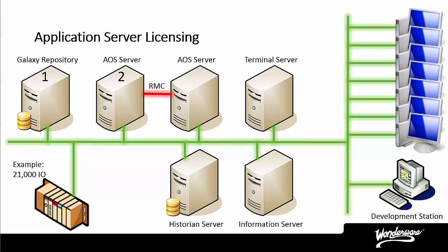The Galaxy Repository is always the first platform in the application. The AOS computer runs objects that represent pieces of equipment or functions to be performed. If you would like a more reliable system, you can add a second AOS computer for redundancy. If you will be hosting your HMI application on a terminal server to use thin clients, you will need to count this computer as well, and you can have a second terminal server for redundancy, though our example does not show one. The historian computer runs the Wonderware Historian. Not all applications use the Wonderware Information Server, but if yours does, it is recommended to put a platform on that computer. Our count for the number of platforms is six.